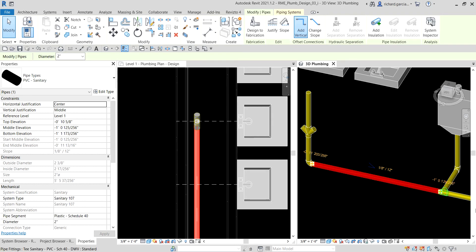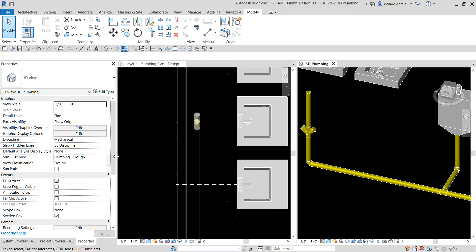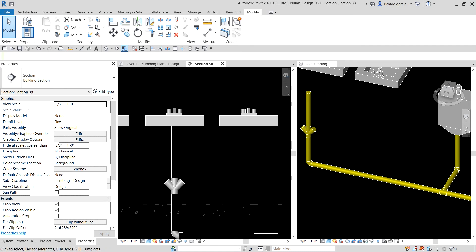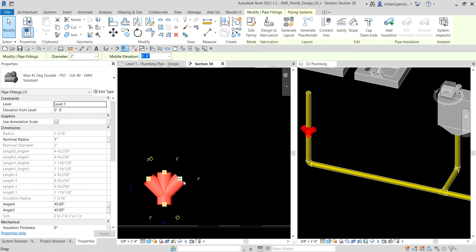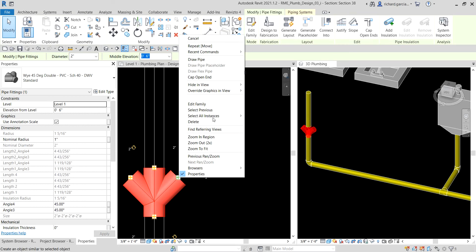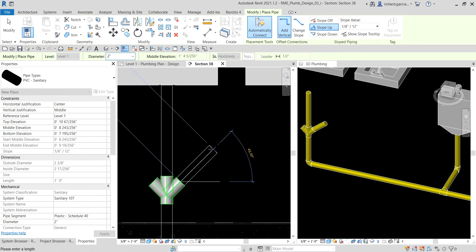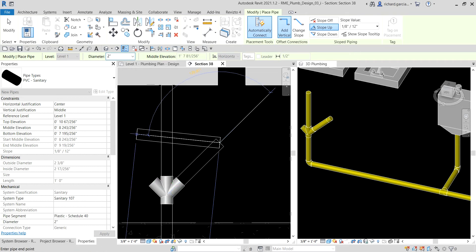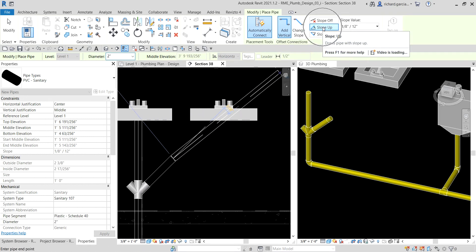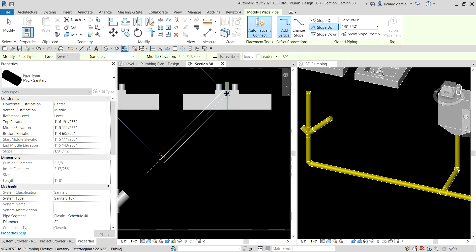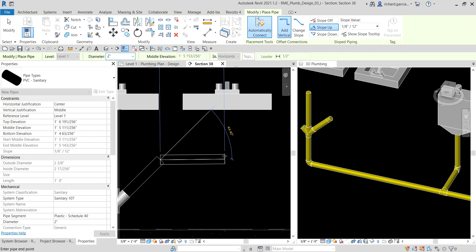Now I'll add pipe stubs to the double-Y fitting. I open the section view by double-clicking the section head in the plan view. I select the fitting, right-click the connector, and choose 'Draw Pipe.' I move the pointer 45 degrees in the correct direction, type '1' for 1 foot, and press Enter. I'll make sure the slope is set to 1/8 inch per foot going in the correct direction.